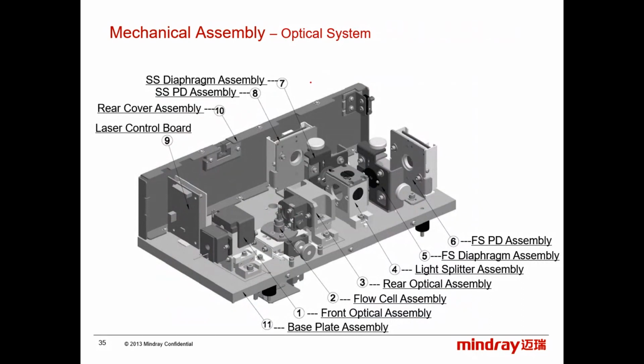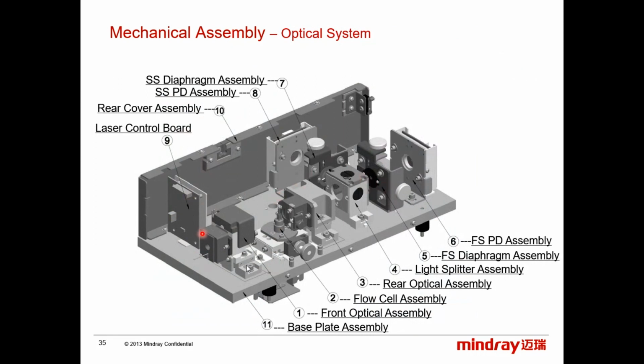All right, the optical system is not very complex. Let's start here. For the optical system, there is no mechanical adjustment needed for this model, or for this optical assembly. You can only replace some specific parts, like the SS diaphragm assembly, the SS photodiode assembly, or FS. Maybe you can change the laser control board and so on. But for the mechanical components, the lenses, you do not touch.